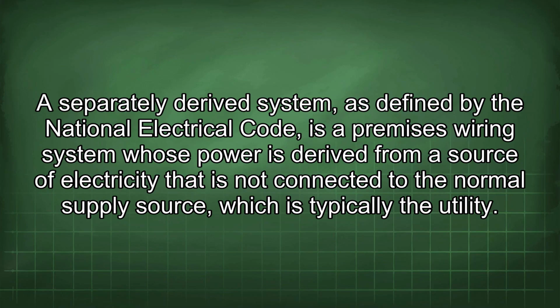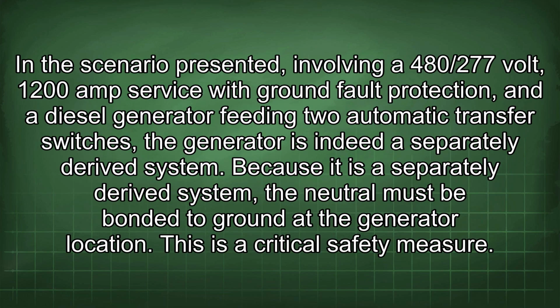A separately derived system, as defined by the National Electrical Code, is a premises wiring system whose power is derived from a source of electricity that is not connected to the normal supply source, which is typically the utility. In the scenario presented, involving a 480/277 volt 1200 amp service with ground fault protection and a diesel generator feeding two automatic transfer switches, the generator is indeed a separately derived system.